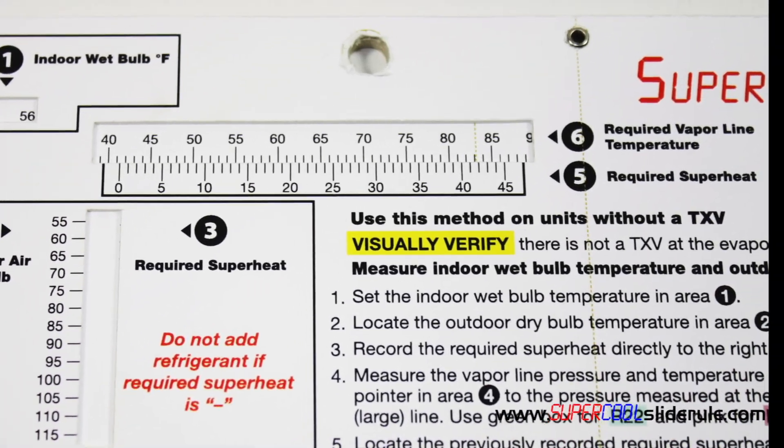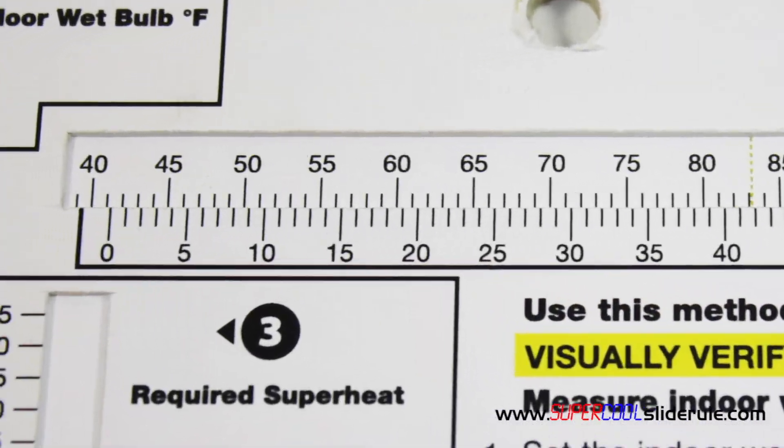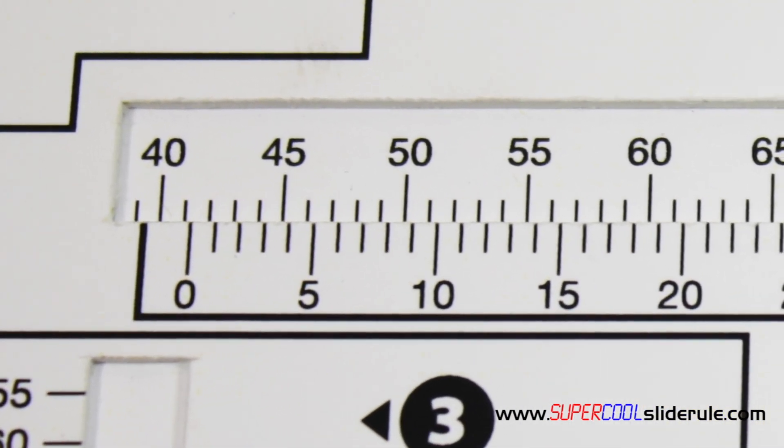We then proceed to box 5 and locate our previously recorded required superheat, which was 10 degrees. Directly above the 10 degree mark is 50. So 50 degrees is our required vapor line temperature.